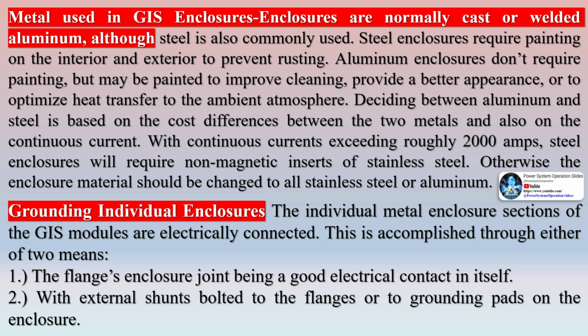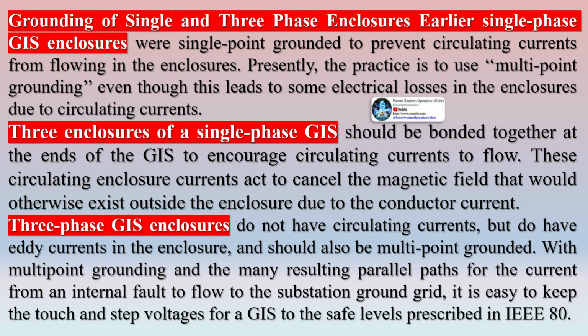Enclosures are normally cast or welded aluminum, although steel is also commonly used. Steel enclosures require painting on the interior and exterior to prevent rusting. Aluminum enclosures don't require painting, but may be painted to improve cleaning, provide a better appearance, or to optimize heat transfer to the ambient atmosphere. Deciding between aluminum and steel is based on the cost differences between the two metals and also on the continuous current. With continuous currents exceeding roughly 2000 amps, steel enclosures will require non-magnetic inserts of stainless steel. Otherwise, the enclosure material should be changed to all stainless steel or aluminum.